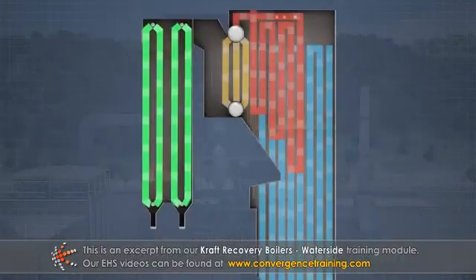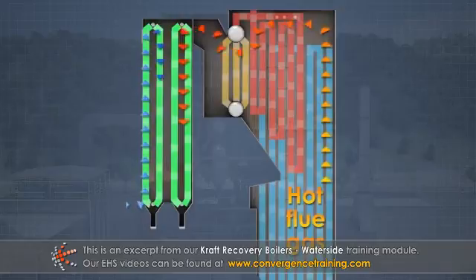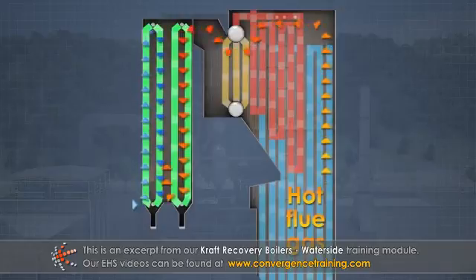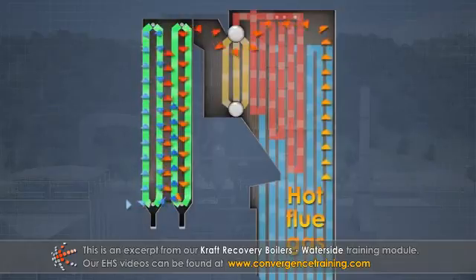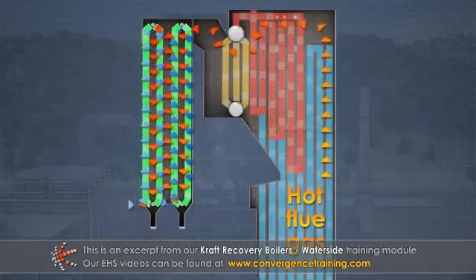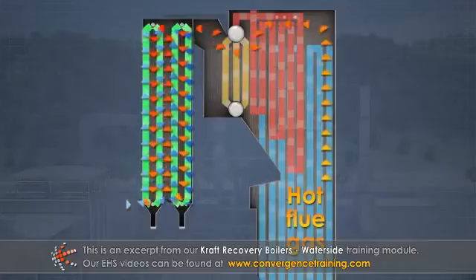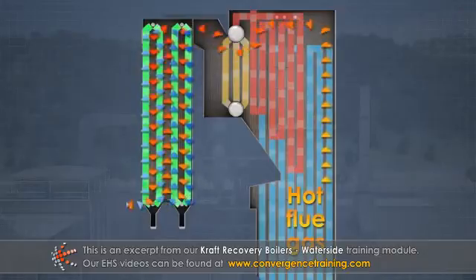Sometimes there are multiple banks of economizer tubes. In this case, the flows are routed in a counter-current fashion such that the coolest incoming water contacts the coolest outgoing gas.